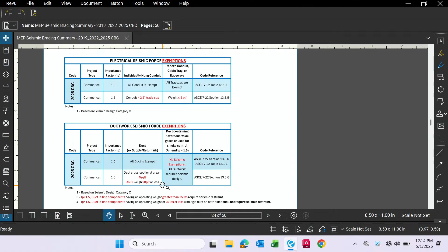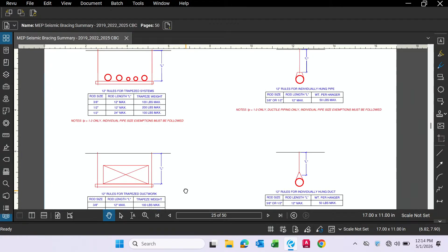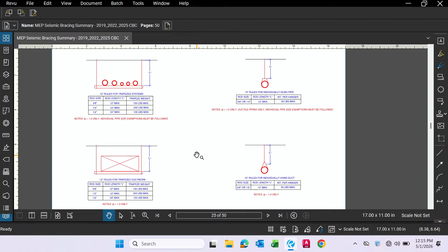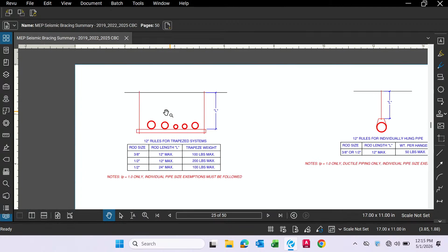Let's see. Did you say, Luke, that there haven't been many changes from 2022 to 2025? Yeah, all these bracing exemptions are the same from 2019 to 2025 California. I don't know if you guys are familiar with the 12-inch exemption, but basically in the old code cycle, they said that if the component or utility is suspended within 12 inches of the structure, it doesn't need to be braced. Under the new code cycle, that exemption has pretty much gone away. Well, it hasn't gone away completely, but it became more difficult to apply.